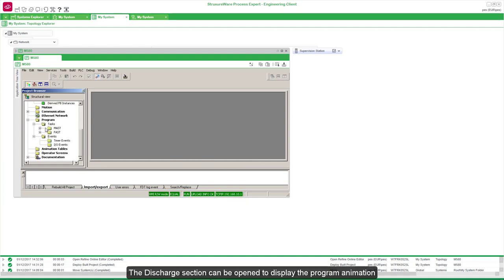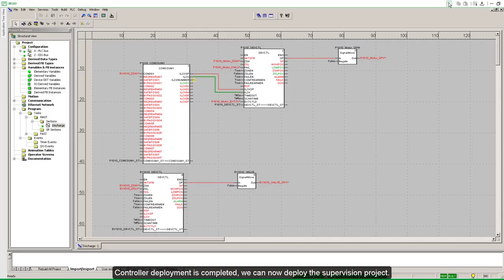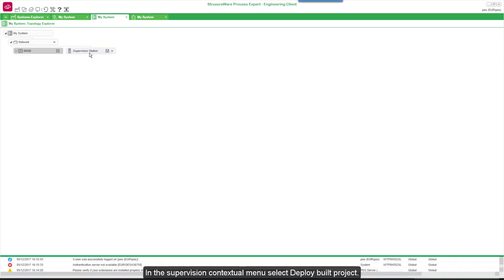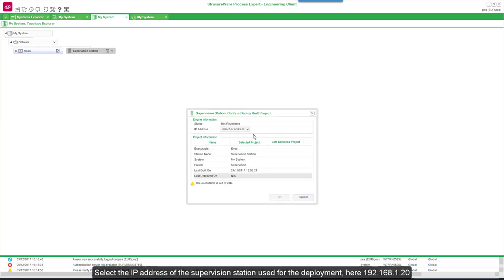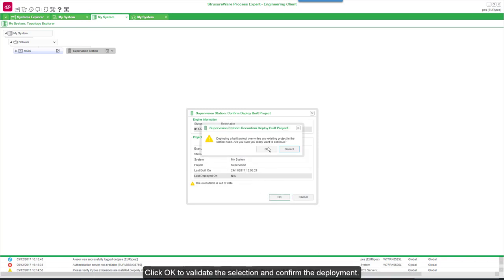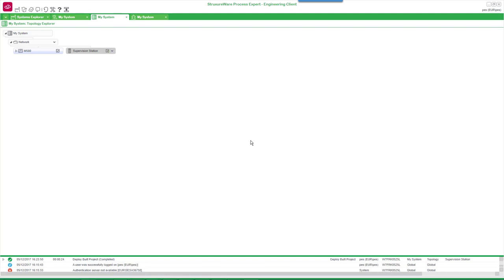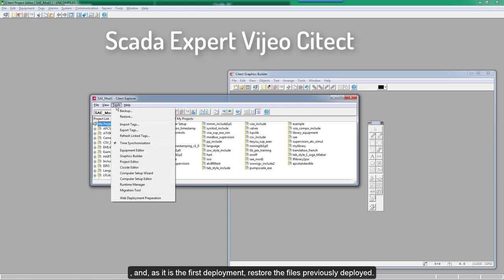The status bar indicates the IP address of the connected controller. The Discharge section can be opened to display the program animation. Controller deployment is completed; we can now deploy the supervision project. In the supervision context menu, select Deploy Build Project, then Supervision. The pop-up window shows the executable mapped to this station; confirm by OK. Select the IP address of the supervision station used for the deployment. Click OK to validate the selection and confirm the deployment. When the deployment is done, we have to open the supervision station and, as it is the first deployment, restore the files previously deployed.